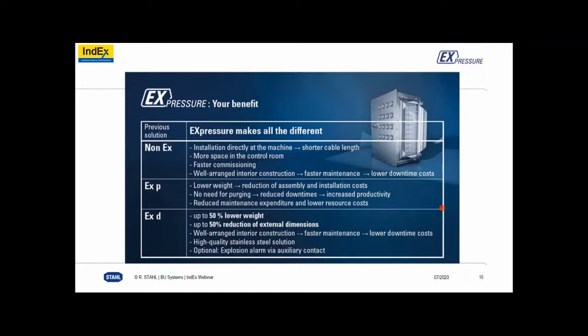With heat, it's less of an issue with an EXD cabinet because it absorbs the heat equally throughout its entire enclosure. Now, somebody else was asking, what is the EXD enclosure and what is the relief? The EXD is the overall enclosure. The EXS is the relief points on the side. So once again, the advantages are that it's like a typical EXD box, but with reduced weight, reduced dimensions, and it's faster and easier to certify, to install, and everything. So it's still as flexible as a regular EXD box with added advantages, and you can add an EXE connection chamber.